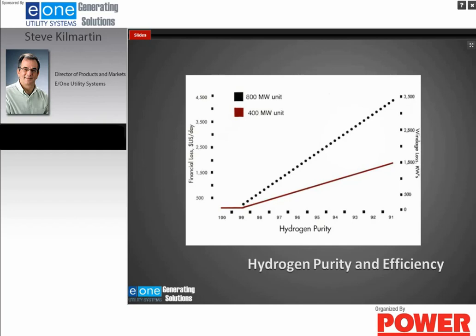This chart indicates the effect of having pure hydrogen. As you can see, the purer the hydrogen, the lower the windage loss, which equates to lower financial losses. There are two different slopes. One is for a 400 megawatt generator, less financial impact with having higher purity versus lower purity, and then an 800 megawatt unit, where you can see it's significant when you go from 91% to 98 or 99%, the windage losses that occur and the loss in financial dollars.